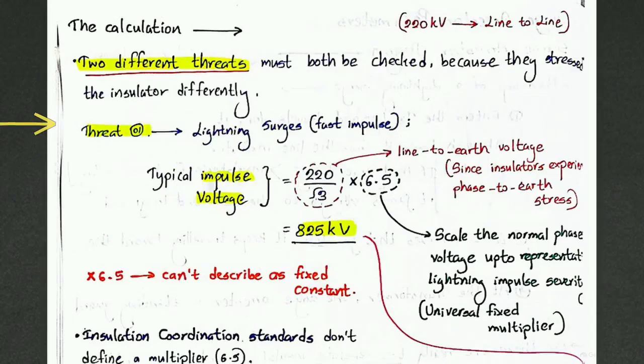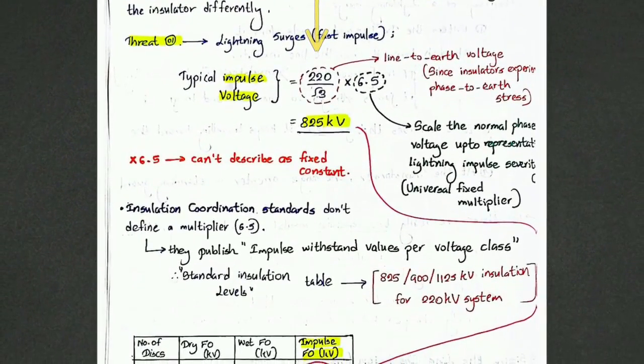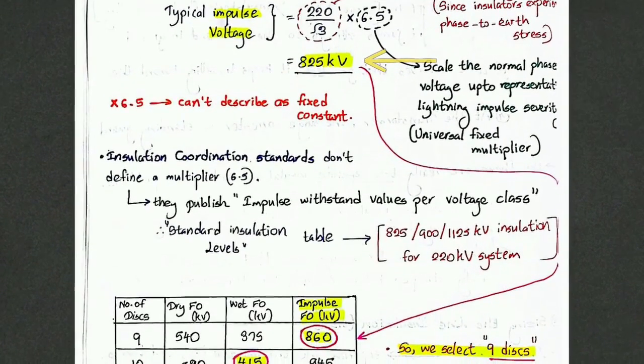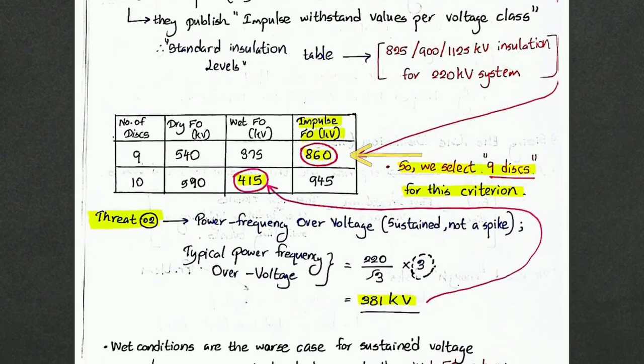This calculation shows our first major hurdle. Threat 1, lightning surges. Because insulators experience phase-to-earth stress, we have to scale our 220 kilovolt line-to-line voltage down. We do this by dividing by the square root of 3 before applying the impulse multiplier. That math gives us an 825 kilovolt typical impulse. Looking at standard insulation tables, a 9-disc string provides an 860 kilovolt impulse withstand. For lightning, 9 discs clear the bar.